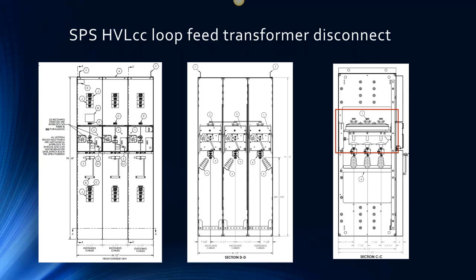Mike Bukovitz, you're familiar with this switch. Would you like to comment? Absolutely. Other benefits of this switch, in addition to the obvious real estate space savings that you can see from these drawings, are that, and you have to look in the middle of the switch, you can actually see it in Michael's drawings, two little circles. If you look in the switch mechanism itself, it's on the left-hand side, centered. Those are arc-rated viewing windows. So the top window shows visible confirmation of grounding, and the bottom window shows visible confirmation of phase blade disconnect.